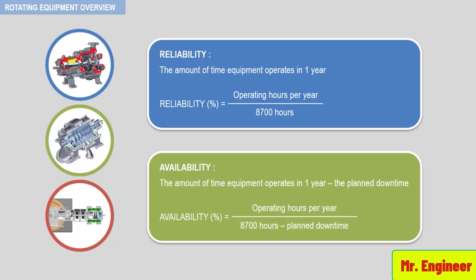Remember, even though the unit may be down for a short period, the time necessary to bring the process back within specification may be significantly longer. It is very valuable to obtain the product revenue figure for the unit in which you are working, as it can significantly influence your management in terms of decision making. Upset conditions with any piece of rotating equipment can occur in a very short period of time. The requirements for reliable operation — a minimum of three years continuous run — will require an enormous amount of equipment revolutions, all on a very thin film of lubricating oil. Failure to maintain this film is one of the major reasons for reduced equipment availability.